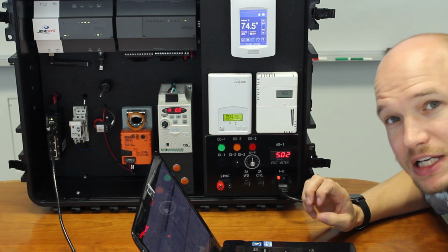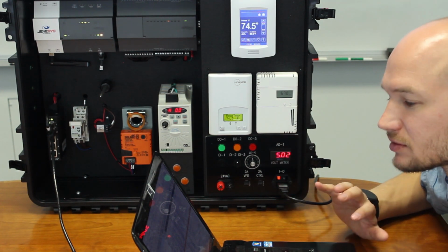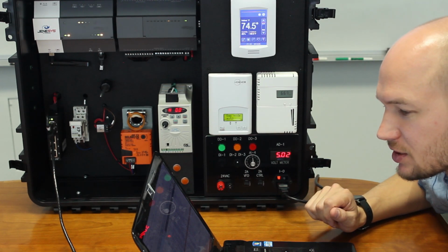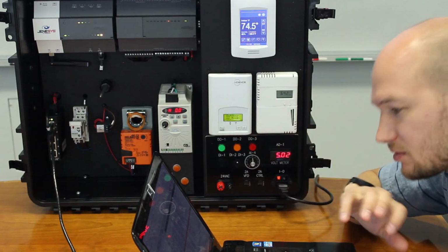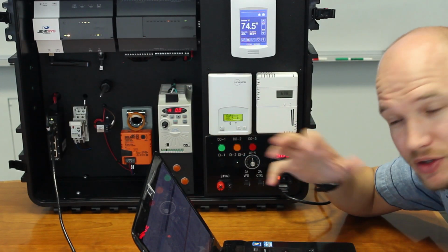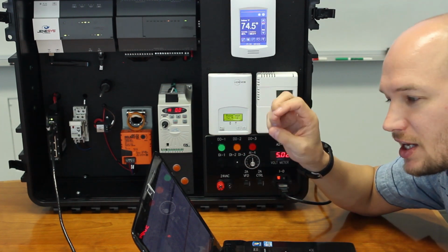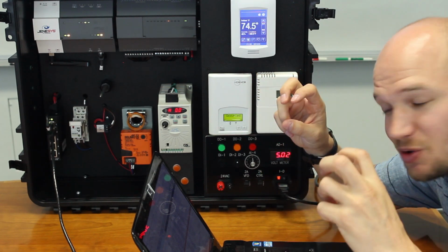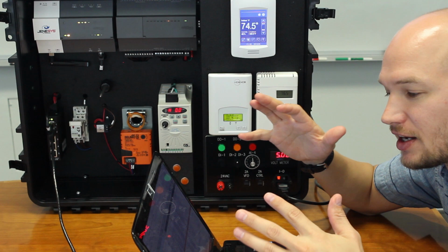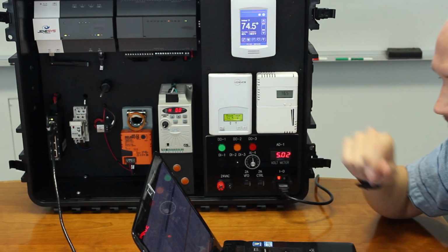And so likewise, if we brought this temperature down, we're going to see the cooling switch over. And we'll see some of the changes that display on the computer. So you can see the swap over, heating went zero, cooling went 37%. Now it would run until it started to cool the room. It would get feedback from the thermostat or the set points or the room temperatures, and it would use its algorithm, its smart controller brain, and change that demand for cooling.